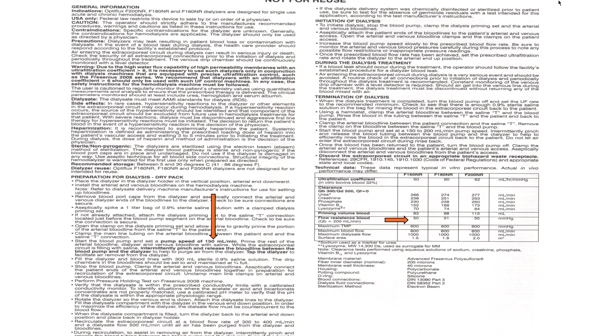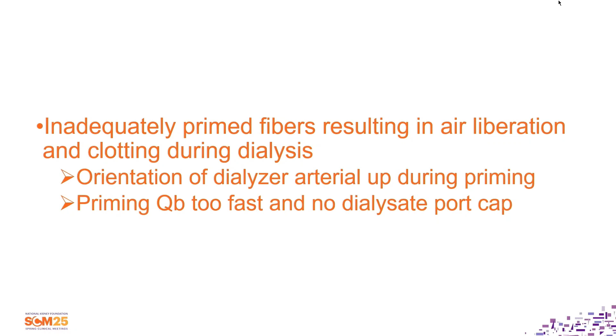So being so permeable to water, what happens is that if that cap is not in place, what does water or normal saline tend to do? It takes its least path of resistance. So, resulting in inadequately primed fibers, resulting in air liberation and clotting during dialysis. And two causes are orientation of the dialyzer arterial end up during priming and priming too fast. So, how many of your practitioners, or how many times have you experienced someone saying, I've got air in my line, I don't know where it's coming from? It could be coming from the fibers.